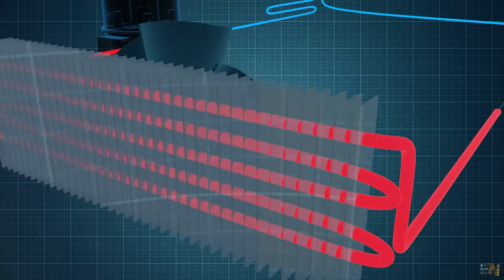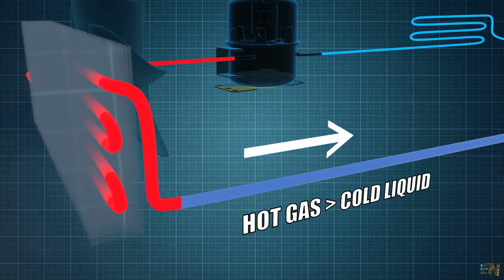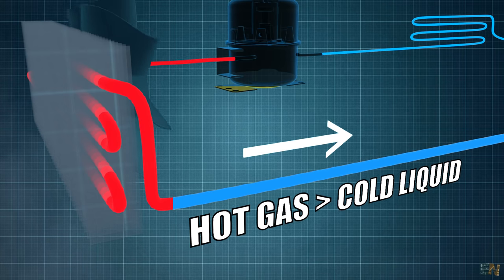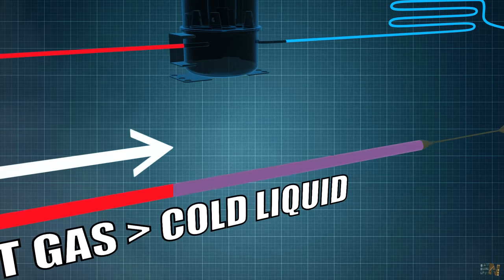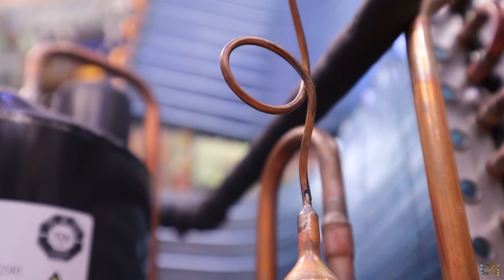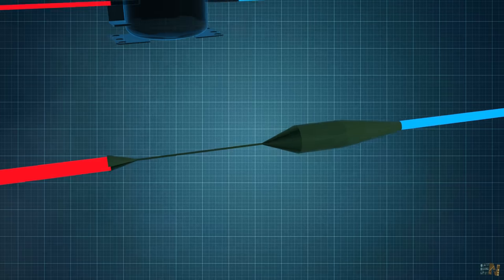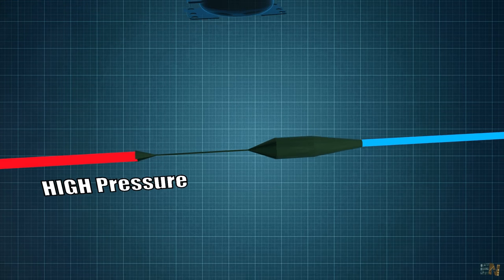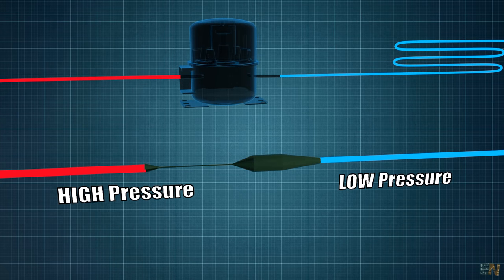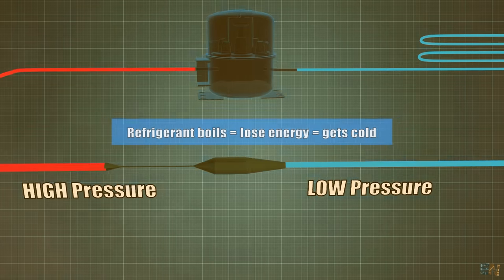Now at the output of the condenser we have that expansion valve which in our case is based on a capillary tube which is just a long copper tube with a very small internal diameter in order to restrict the refrigerant flow. If the flow is restricted, like this we can separate the high pressure on one side and the low pressure on the other side. But when the pressure drops, the refrigerant will turn back into a gas.